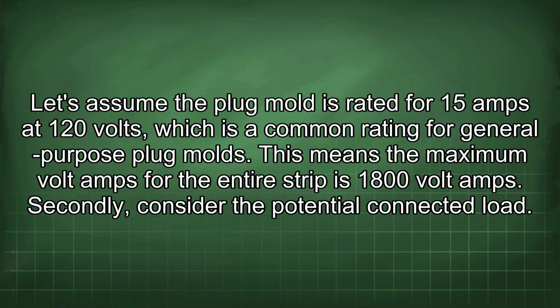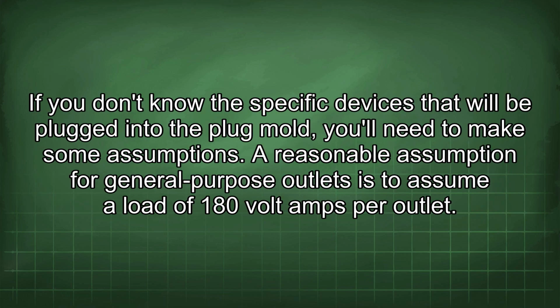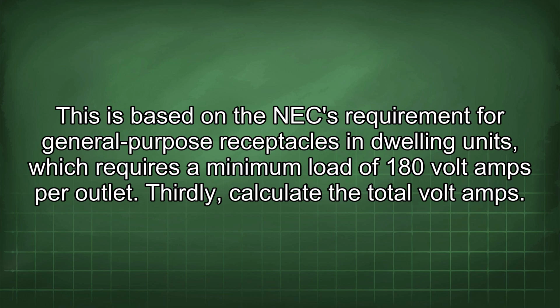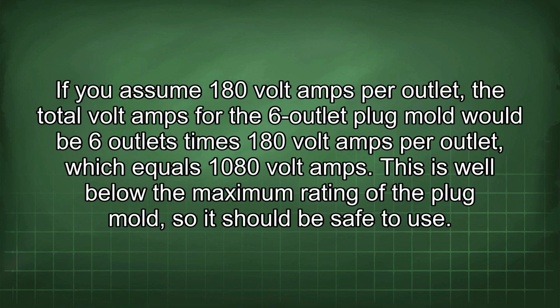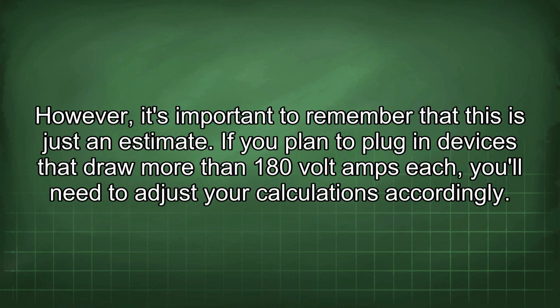Secondly, consider the potential connected load. If you don't know the specific devices that will be plugged into the plug mold, you'll need to make some assumptions. A reasonable assumption for general-purpose outlets is to assume a load of 180 volt amps per outlet. This is based on the NEC requirement for general-purpose receptacles in dwelling units, which requires a minimum load of 180 volt amps per outlet. Thirdly, calculate the total voltamps. If you assume 180 volt amps per outlet, the total voltamps for the 6-outlet plug mold would be 6 outlets times 180 volt amps per outlet, which equals 1080 volt amps. This is well below the maximum rating of the plug mold, so it should be safe to use. However, it's important to remember that this is just an estimate.